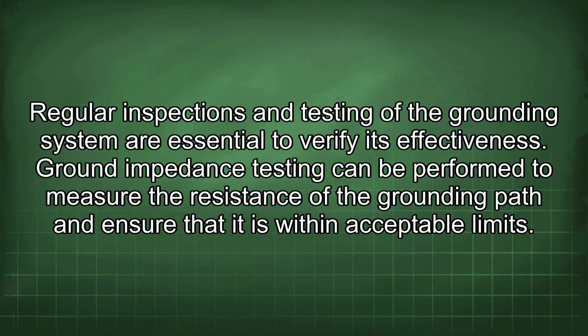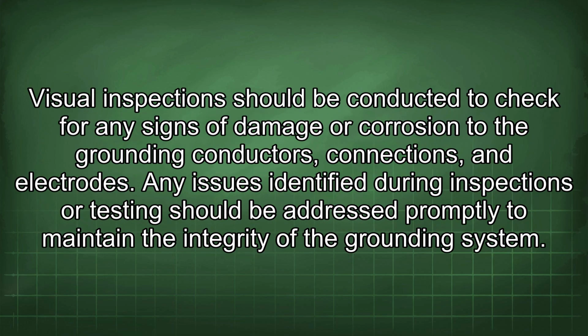Ground impedance testing can be performed to measure the resistance of the grounding path and ensure that it is within acceptable limits. Visual inspections should be conducted to check for any signs of damage or corrosion to the grounding conductors, connections, and electrodes. Any issues identified during inspections or testing should be addressed promptly to maintain the integrity of the grounding system.